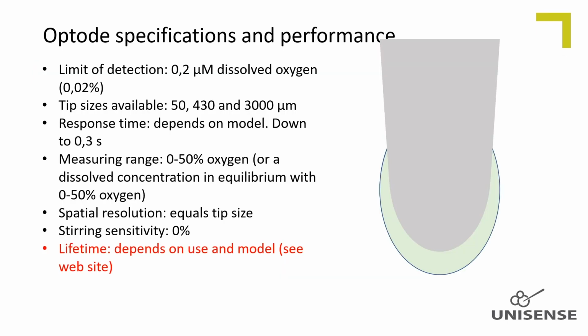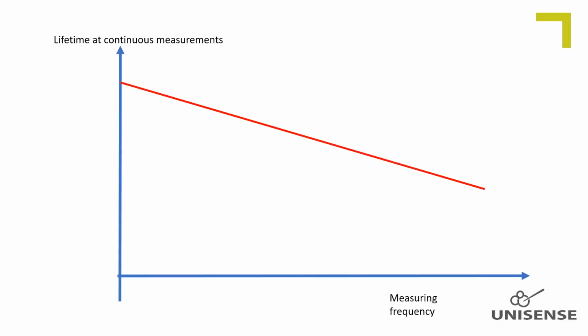The lifetime depends heavily on use and model. The lifetime for non-physically damaged optodes is a function of how much dye the optode tip carries and the tip bleaching rates. Bleaching itself is a function of the number of measurements taken, because the dye must be illuminated every time a measurement is taken, and it is the illumination which causes the bleaching. Therefore, lifetime is given as a guaranteed number of measurements and not the length of a period of measurements. If the optode is used for continuous measurements, the time to reach end of life is linearly dependent on the frequency used during these measurements.